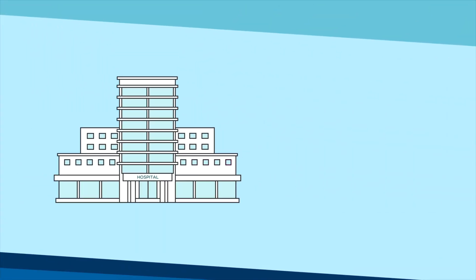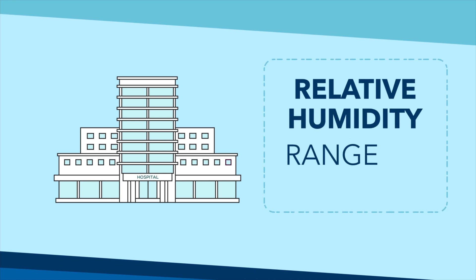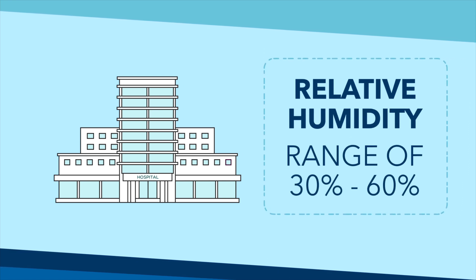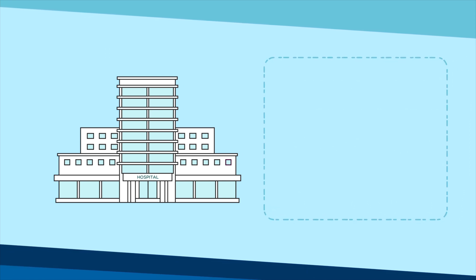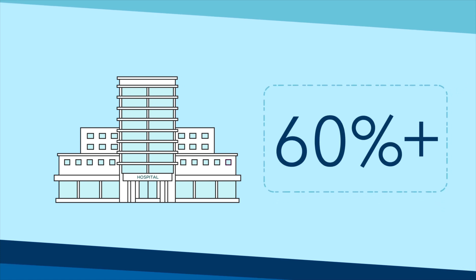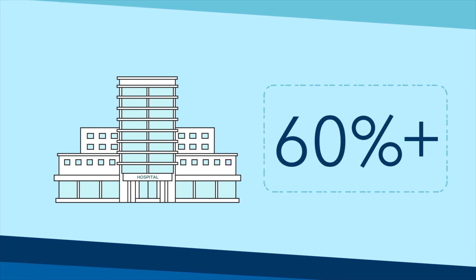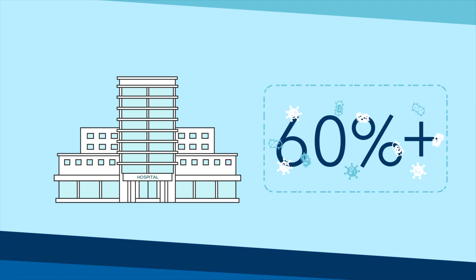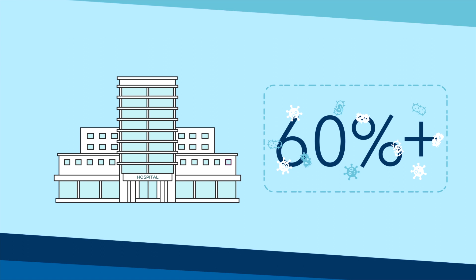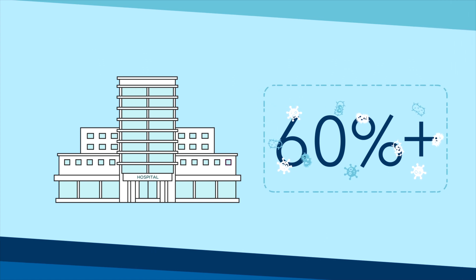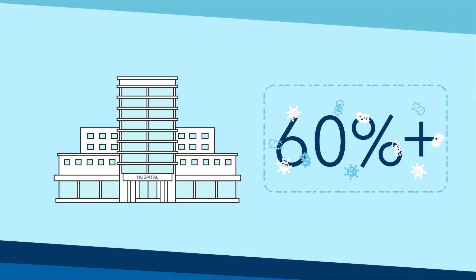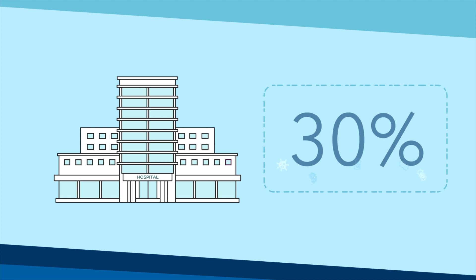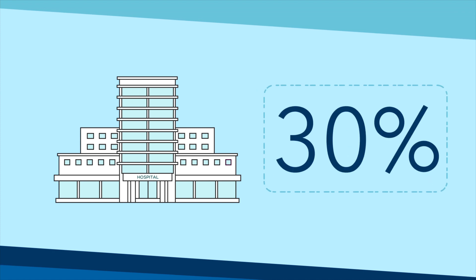Most areas of the hospital have minimum and maximum relative humidity ranges of 30% to 60%. When the relative humidity is above 60%, it not only causes patient discomfort, but it can begin to promote fungal growth. On the other hand, we need some humidity in the air because it helps reduce how far germs can travel in the air, which is why most areas have a minimum of 30% relative humidity.